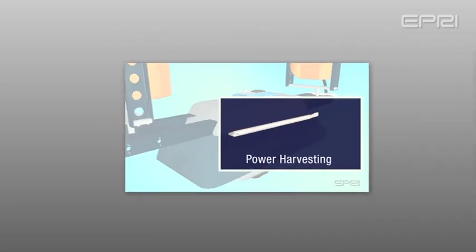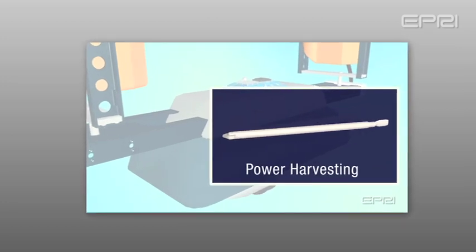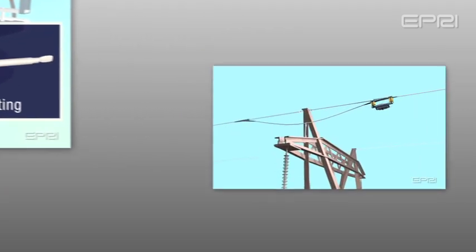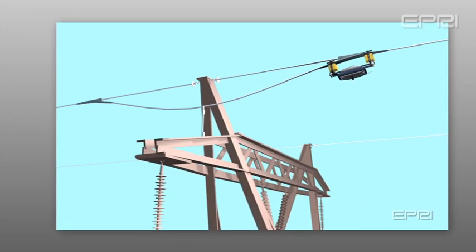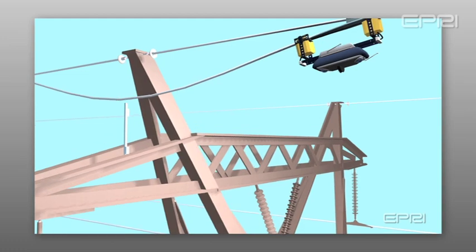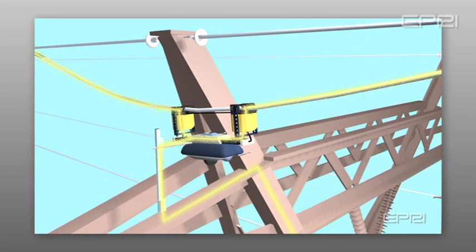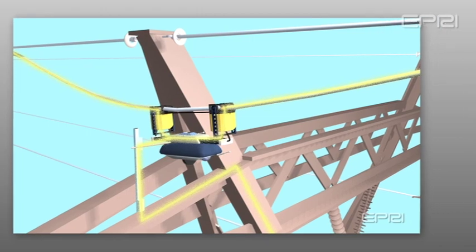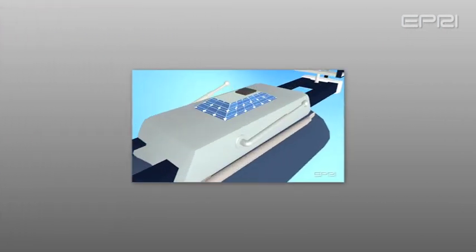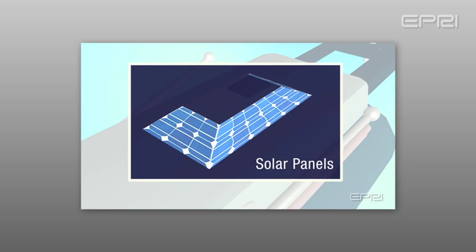The method of powering the robot developed into a power harvesting system that initiated induced currents to flow locally in the transmission line's shield wire. Energy is harvested from these currents to recharge the robot's batteries. A mechanical arm bridges out the shield wire insulators, making positive contact with the structure and recharging onboard batteries. A small array of solar cells remains atop the robot to provide a backup power source for motion, communications, and processing.